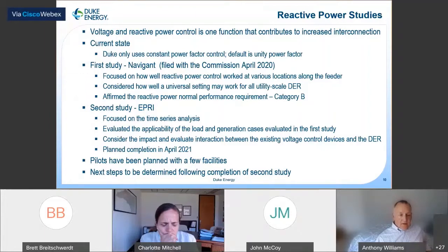We also considered the impact and evaluated the interaction between the existing voltage control devices and the DER that would have reactive power control. In the first study, since it's a fixed load case, it was easier to set devices on the feeder as they should be for that load condition. Those devices might be load tap changers, voltage regulators, or capacitors. But when you start sequencing throughout the hours of the day with various load levels, all those devices may change, or have the potential to change state, so we had to model that and include it in the study as well. That study should be wrapping up in the next couple of weeks.